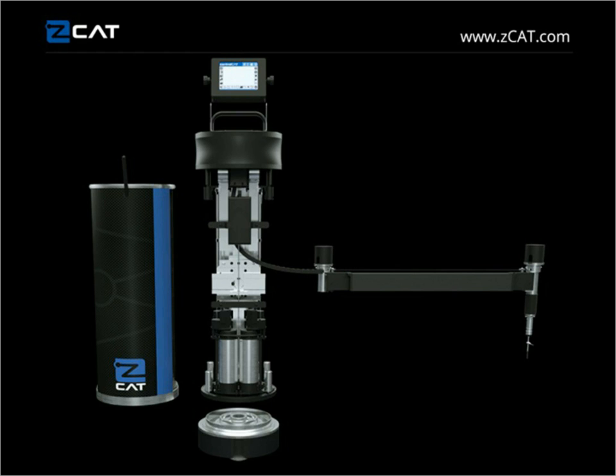kind of broken out, but those motors are driven by, there's a rotary encoder for position purposes only on those motors to drive it to the right location. It will then go to that location and then they'll slow down to the speed where we want to take measurements at. So we're using a combination of Heidenhain and Renishaw rotary encoders, depending on which one we're talking about. We're using Renishaw tape scales in the cross-axis and the Z-axis.